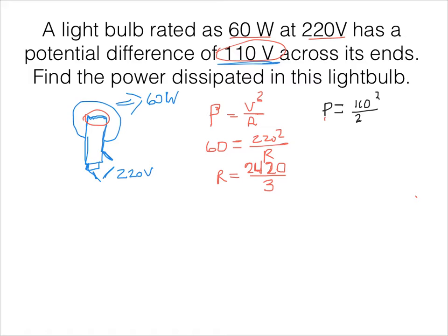So 110 squared divided by 2,420 over 3. And when I put that into my calculator, I will get a power rating of 15 watts.